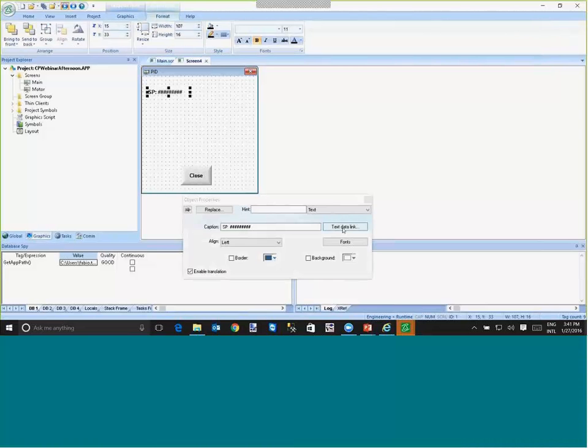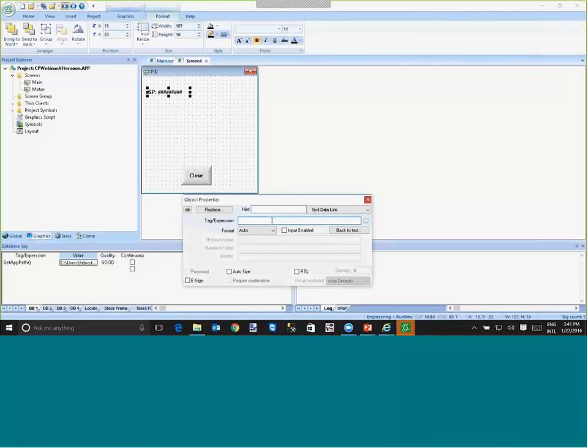and here on this object, I want to show the tag PID A.setPoint. But I want to make it dynamic. I want to be able to open this pop-up and show, for instance, the PID B.setPoint. So I make it a custom property called, for example, PID. Could be any name, but #, custom property name, colon, default value, PID A.setPoint.